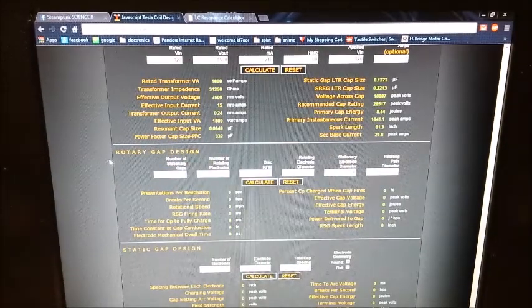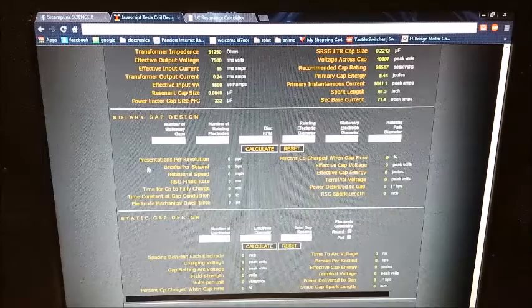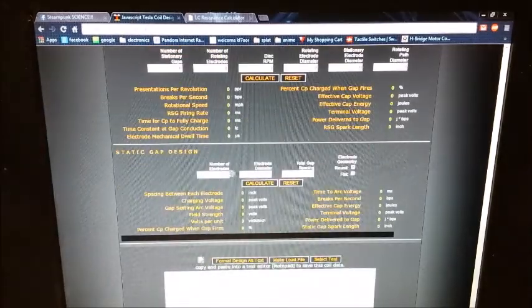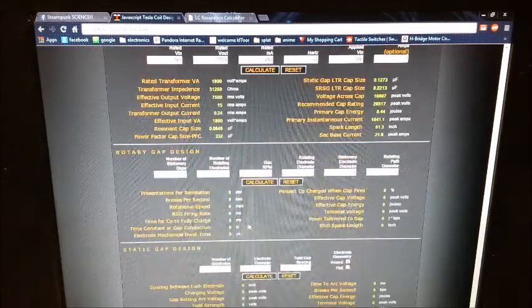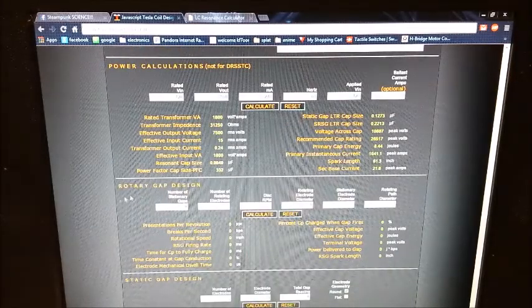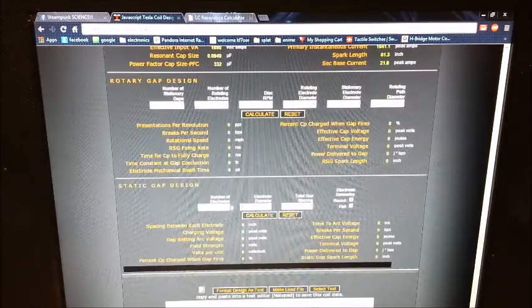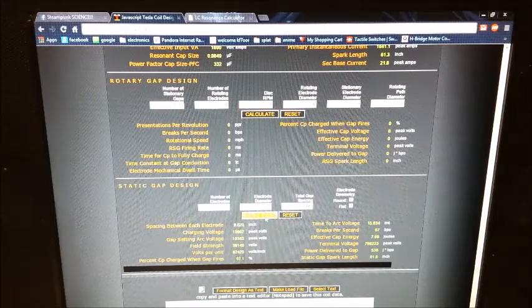We're going to kind of go down. This is a rotary gap design. I actually have a static gap. I'm going to go ahead and put this in. Now again, you cannot enter this unless you enter everything above except for rotary gap. You don't have to have that. Mine's a static. I'm basing it off of 6 electrodes, each with a diameter of 0.5 inches because it's half-inch copper tubing. My total spacing, I'm going to put 0.125, so 1/8 of an inch. Pretty good spacing. It'll tell you down here.